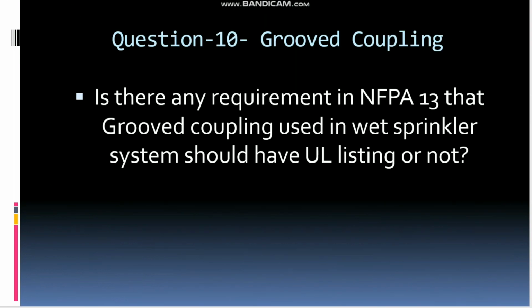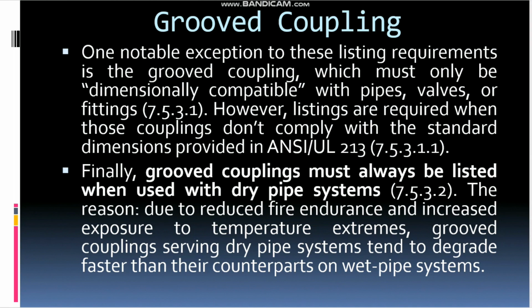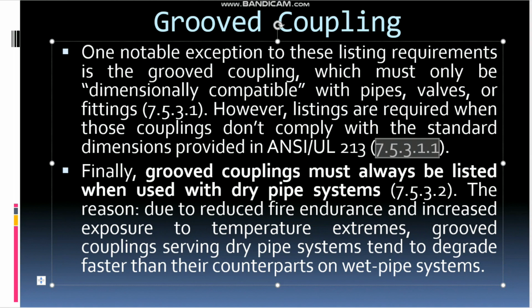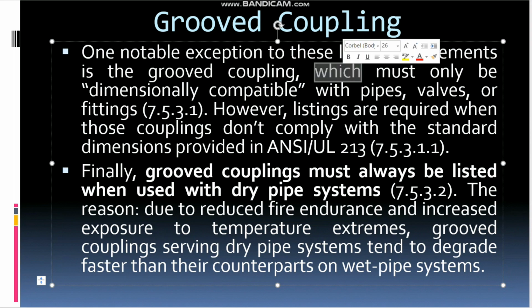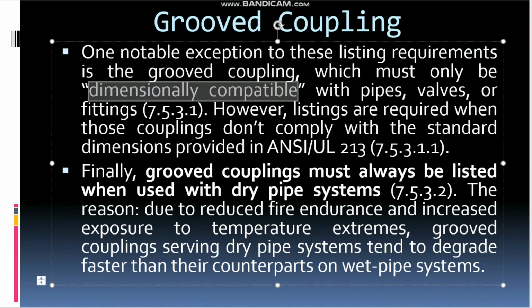Then coming to the joining method: for the smaller sizes up to 50 mm we use the threaded one, and for sizes exceeding 50 mm we go with the grooved coupling. So the question here is: is there any requirement in NFPA stating that grooved couplings used in a wet sprinkler system should have UL listing or not? If you see NFPA 13 7.5.3.1.1, there is an interesting thing here. One notable exception to this listing requirement is the grooved coupling, which must only be dimensionally compatible. So that is the condition.